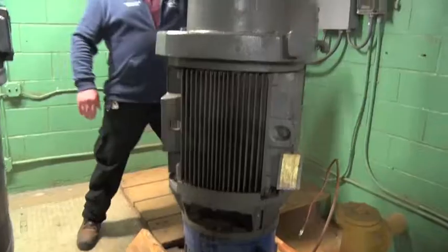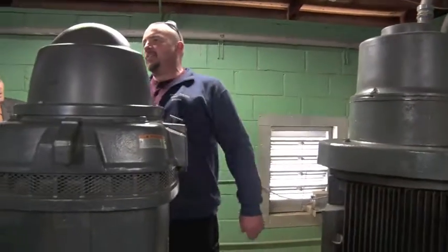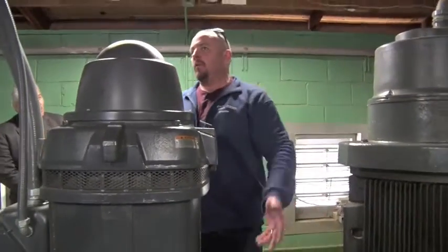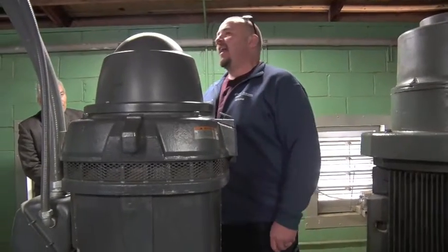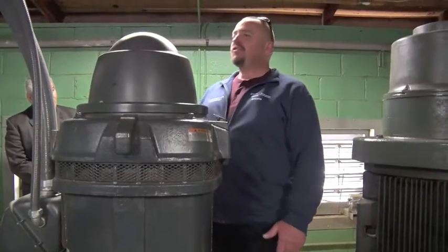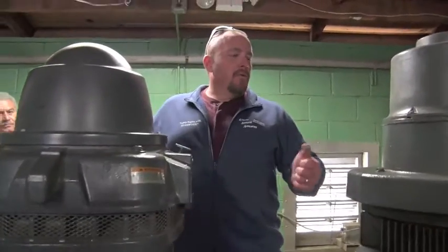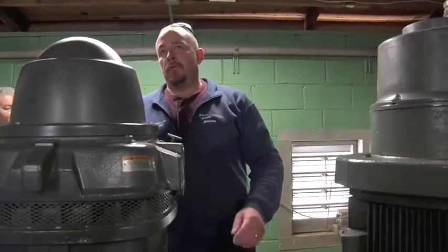Right now from this point, this is 37 feet down is actually called dynamic water level. When you're dealing with wells, static water level is a well that's not in service. That's a static groundwater level. When a well's in service, it's called dynamic level. And right now we're pulling 2.5 million gallons a day out of this, maintaining that level.